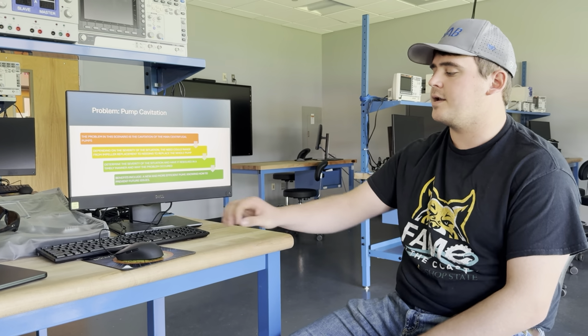Our problem: pump cavitation. The problem in this scenario is the cavitation of our main centrifugal pumps. Depending on the severity of this situation, the solution could easily range from replacing the pump's impeller to replacing the pump entirely. Some of the benefits after this project is done will include new and more efficient pumps and knowing how to diagnose and repair future issues.